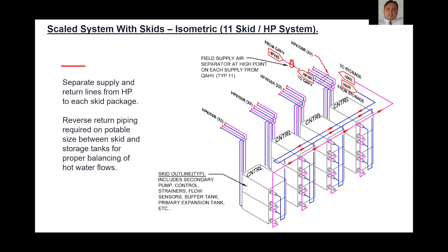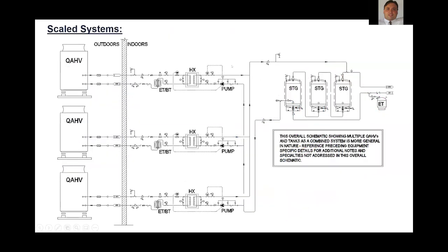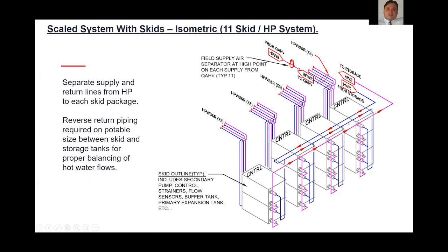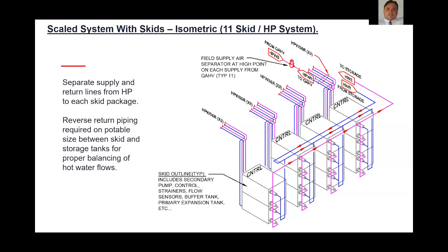So looking at a skid type installation, and this is indicative of one of the projects we've looked at recently. This is actually a large dormitory with 11 skid packages in this case. Those are indicated by these gray boundaries here in these boxes. Each of those skid packages would contain all this componentry that you see here on the screen between the primary and secondary side with the controls. And so you would have dedicated water lines, supply and return, from each of those heat pump water heaters. And then on the storage side, you would basically reverse return, just like this illustrates in this drawing. You would reverse return each of those skid packages accordingly.